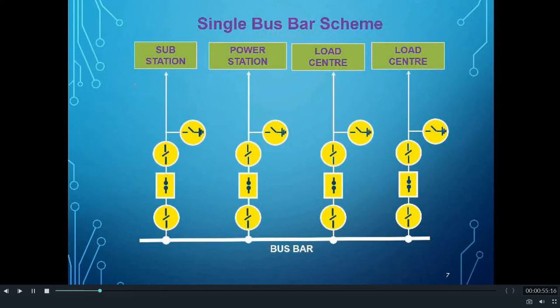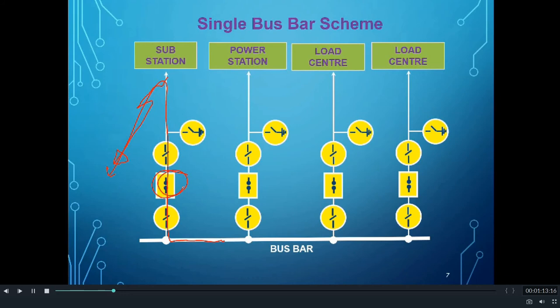Regarding the busbar scheme, I have already uploaded videos. In this busbar scheme, if we consider there is a fault in one of the feeders, then the direction of the fault current will flow accordingly. So as to clear the fault, the associated circuit breaker of the feeder is supposed to trip. That will further protect the fault from propagating through the bus and also protect all other feeders connected to the bus. But in case of failure of the circuit breaker to operate during a fault, a signal will be generated from that particular feeder to operate all other feeders connected to the busbar.